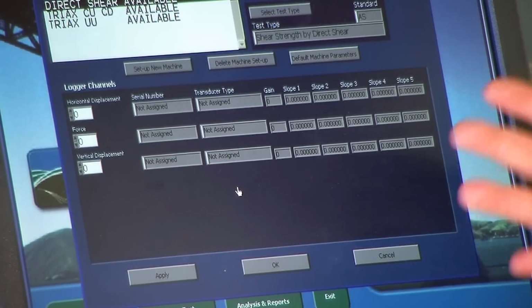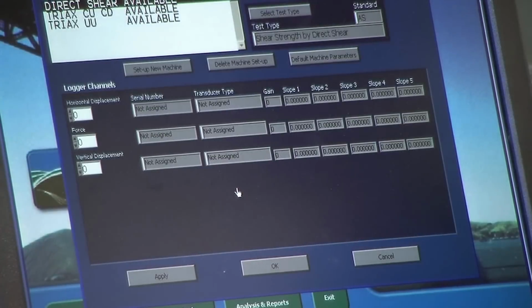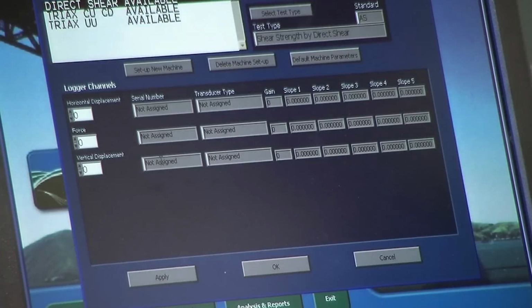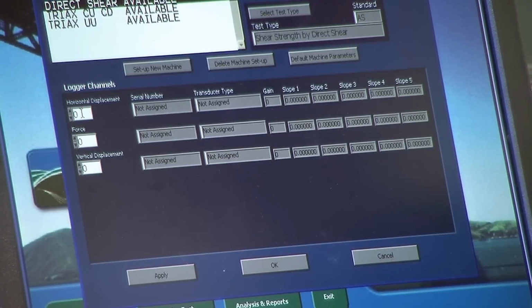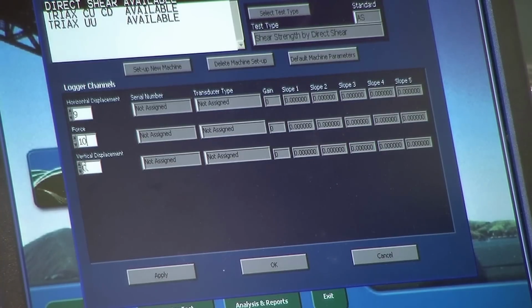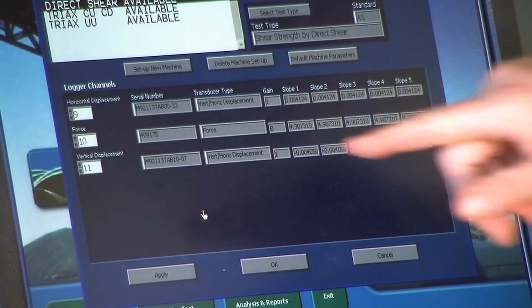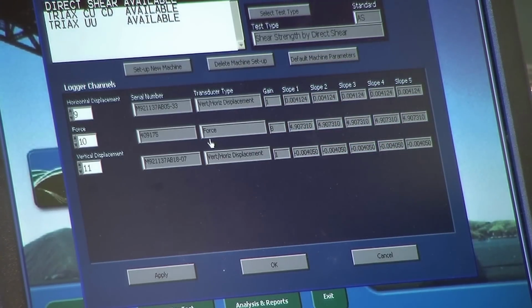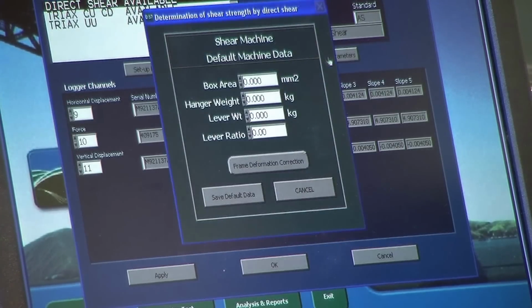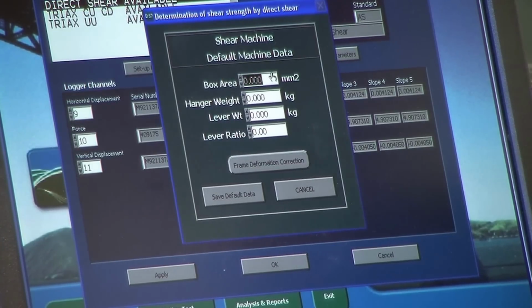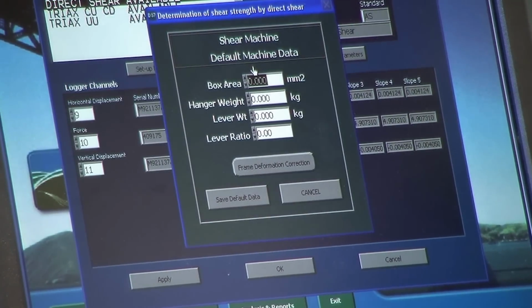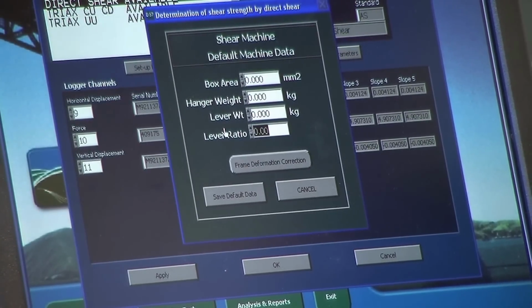Then click OK, and what that does, it automatically brings up which transducers are required for that test, and we need to fill in which channel on the logger we want associated with each one. The horizontal displacement is channel 9, the force is channel 10, and the vertical is channel 11. And then we hit apply, and that automatically brings in all the calibration data that we just verified and inputted and verified within the system. Now we want to go over to default machine parameters, and we can enter in the box area and the lever ratio. The box area may or may not change depending on which size boxes you have. You may want to calculate that. I'll leave that as 0 for now, and we'll calculate it later.